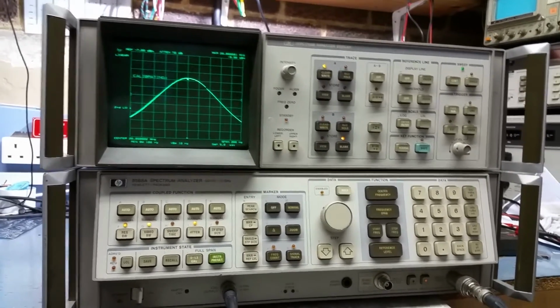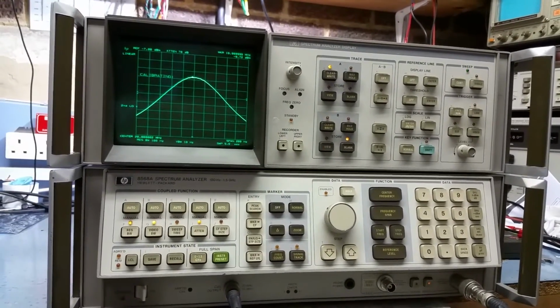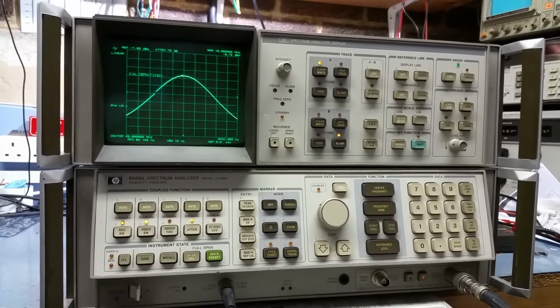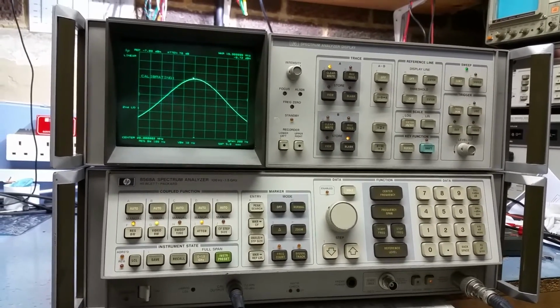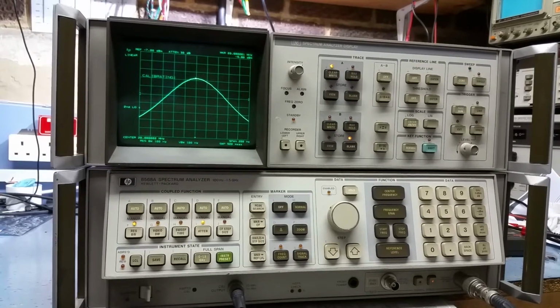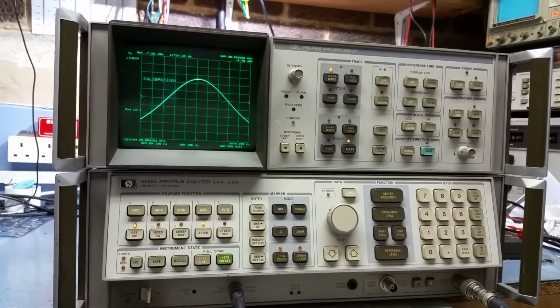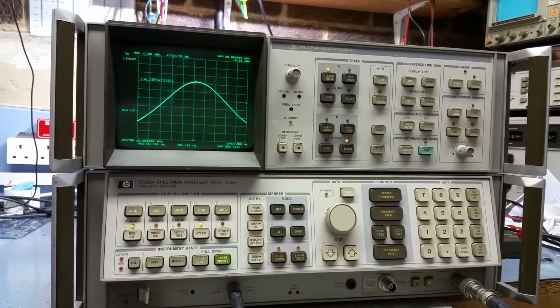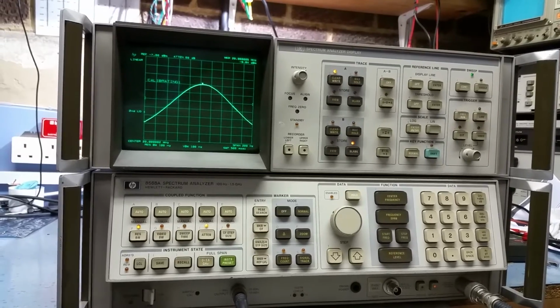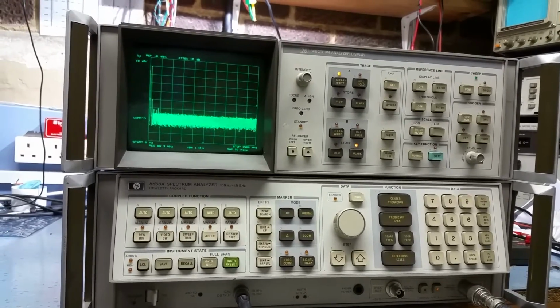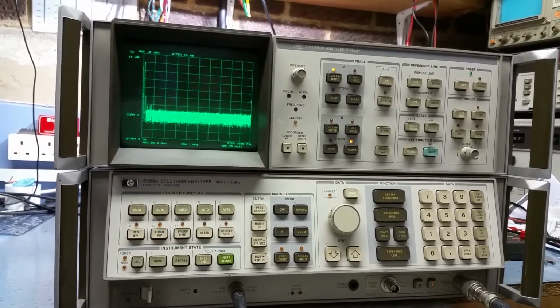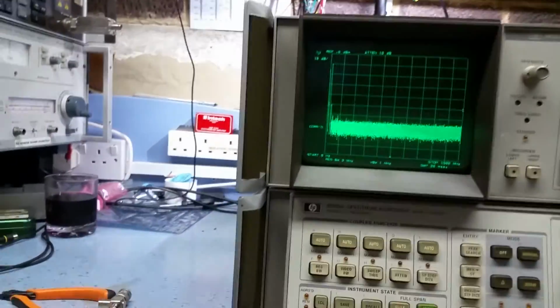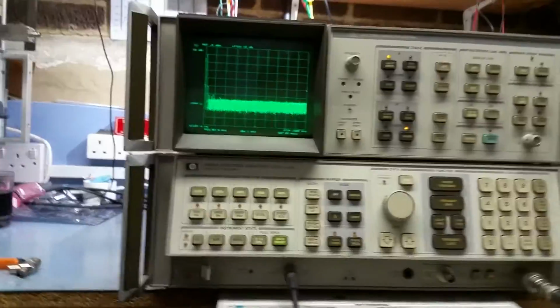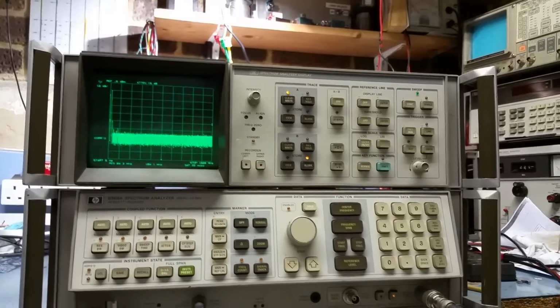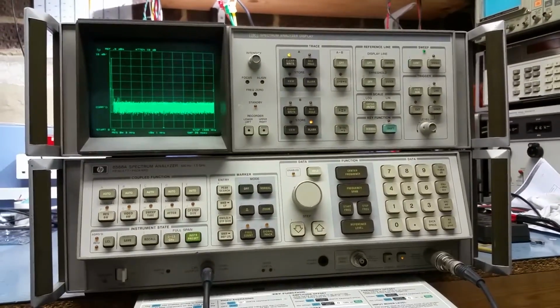And sure enough, the previous cable, which was an old scope probe lead, obviously had some resistance to it, or too high or too low capacitance, or had some strange effect on the response of the output of the calibrator, but it's working fine now. So that's the calibration run performed. So in theory, the spectrum analyzer is in perfect working order.